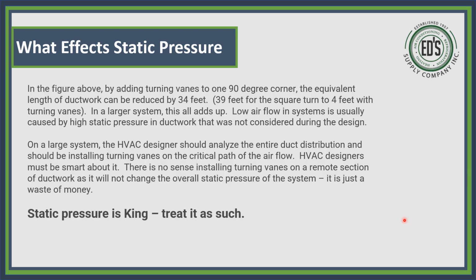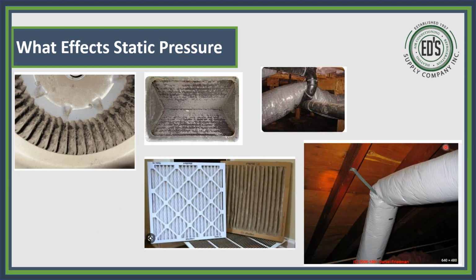Now, if you figure above, by adding turning vanes to a 90-degree corner, you see what the equivalent of the feet is, and they want everything to be 100 feet or less. On a large system, the HVAC designer should analyze the entire duct distribution and should be installing turning vanes on critical paths of airflow if you're using square duct. If you're using round pipe, it's not near as bad. Static pressure is king, so treat it as such.